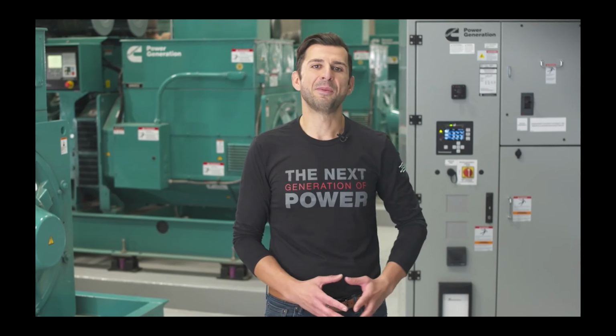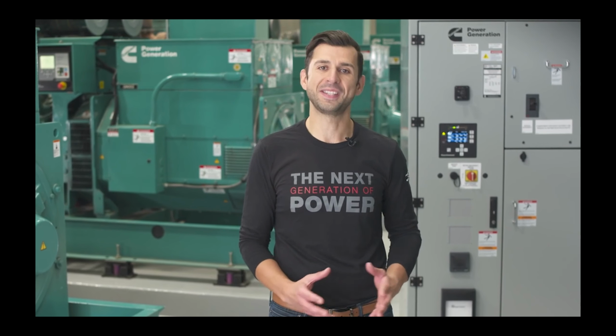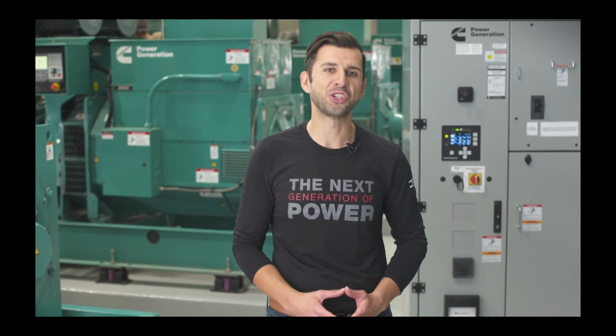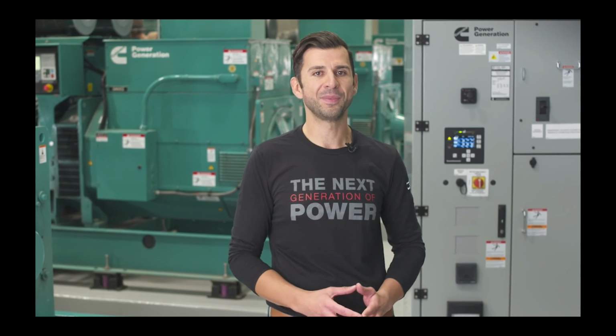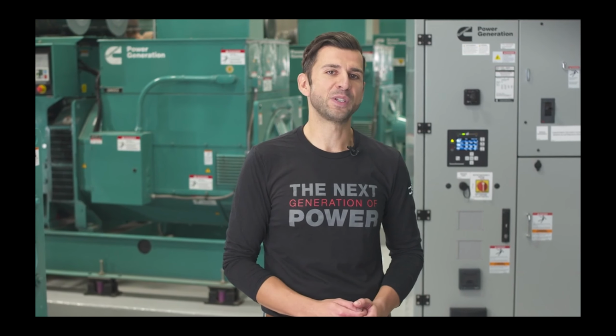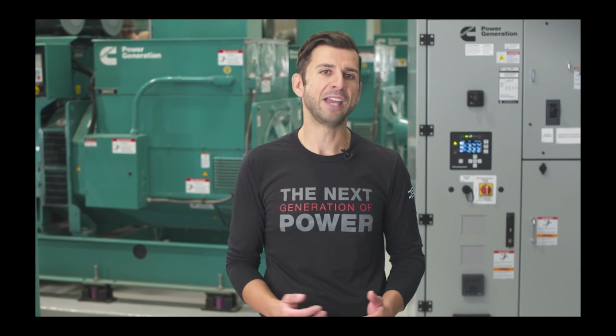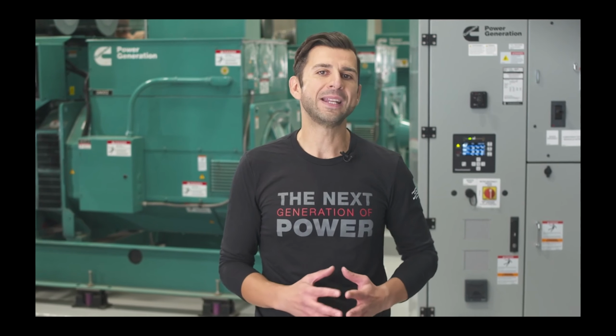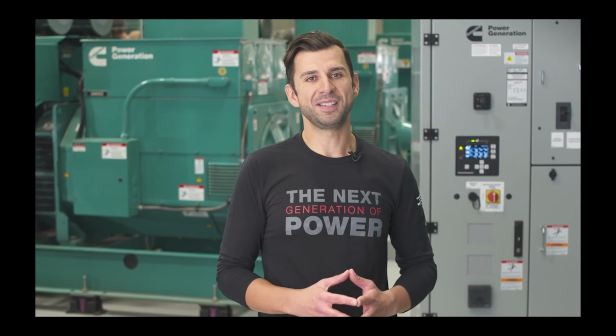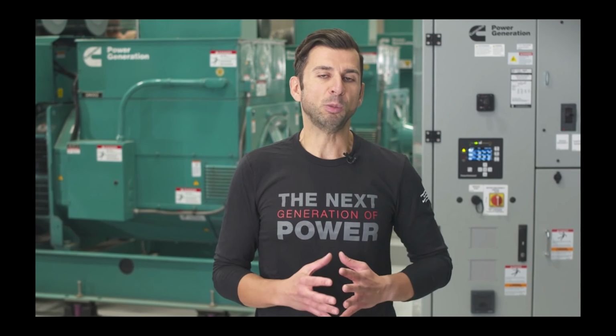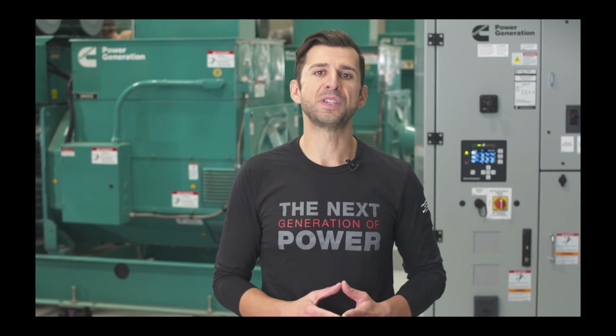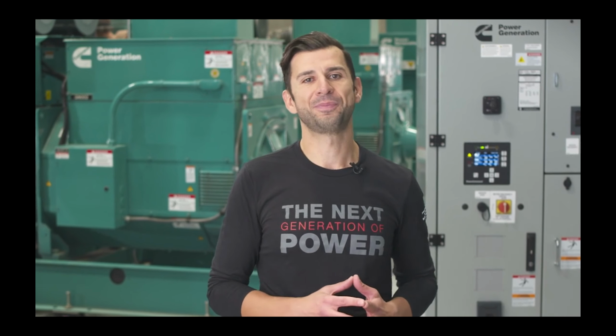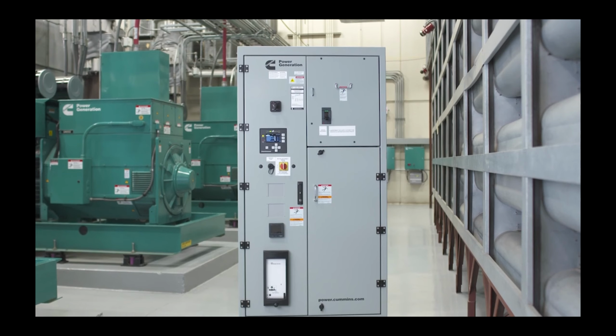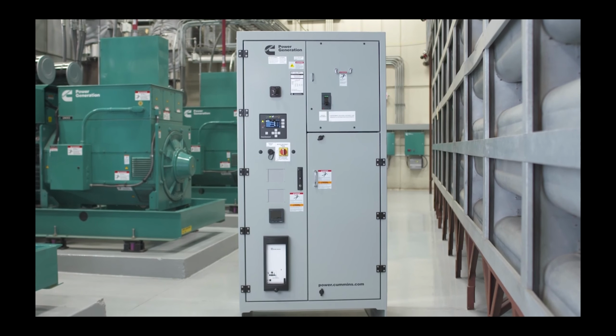I have next to me the Power Command X Series transfer switch C-frame, which is close transition and service entrance rated. For safety reasons, the transfer switch is not fully connected to live AC sources, therefore we cannot demonstrate its full capabilities. So today, we will be focusing on high-level features of the transfer switch and control. The C-frame ranges from 150 to 600 amps.